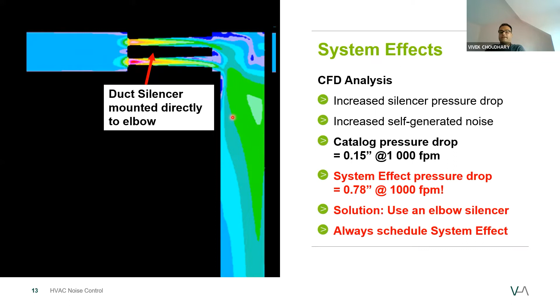So we need to consider what are the right solutions for different applications at the same time. This is how Long Buildings and Vibro-Acoustics, when we work with you guys on any project, this is how we show it. We always show 2 pressure drops. One is ideal pressure drop and second is a system effect pressure drop. This is the maximum pressure drop: once these silencers are installed, it will not cross this pressure drop. So there will be no surprises to the contractor and the building owner after these are installed.